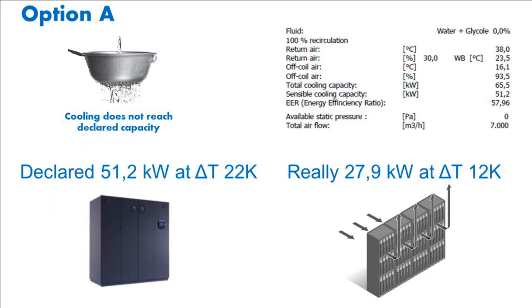Here is the calculation of the CRAC unit, which is designed for air and a total cooling capacity of 65 kW. It is stated that the sensible capacity is 51 kW with an airflow of 7000 m3 per hour with air delta T of 22 Kelvin. In reality, air delta T is determined not by CRAC units but by the servers. And in this case, the CRAC unit will cope only up to 55% of the load. Exceeding this load, the energy consumption of compressors will be increased, but without obvious success.